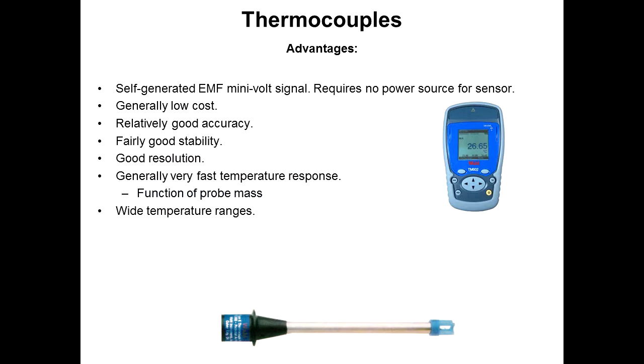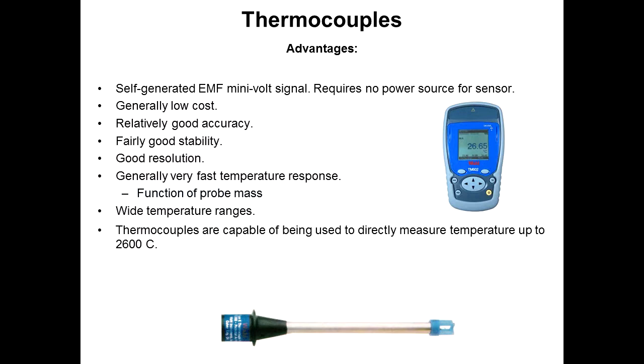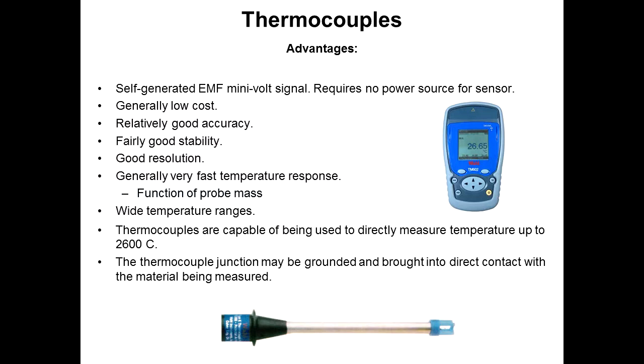Very wide temperature ranges. You can take a thermocouple down to minus 200 Fahrenheit, although very few people go down there because the signal is so weak at those very cold temperatures, you really have to amplify it greatly to read it, all the way up to 2600 C. A thermocouple can be grounded and brought into direct contact with the material being measured, so it's very fast and also very rugged construction.